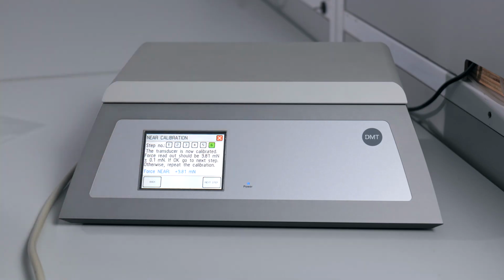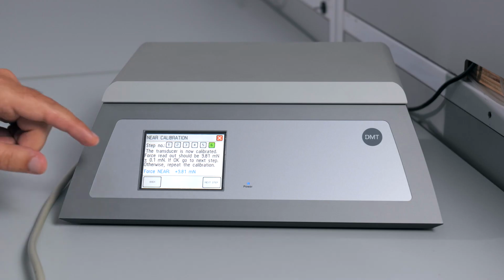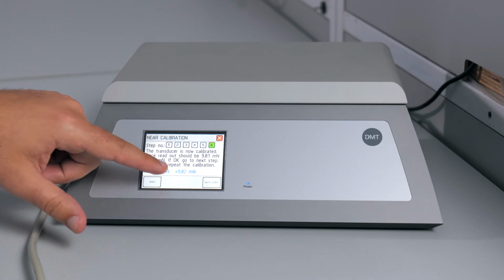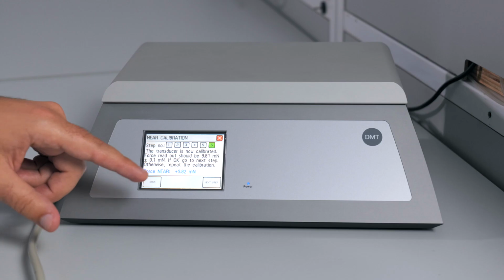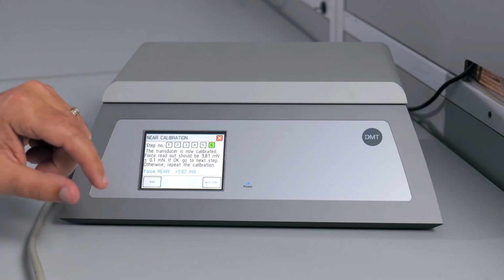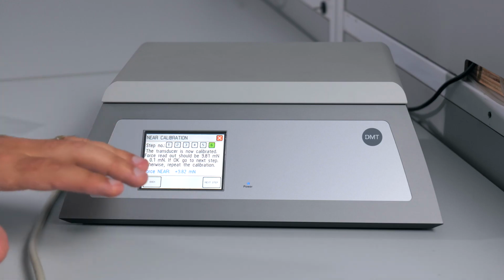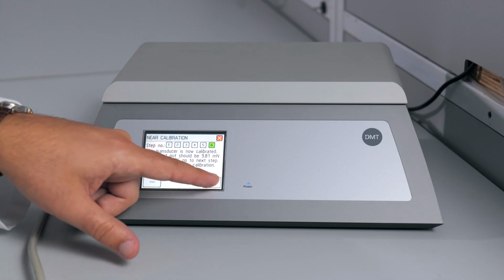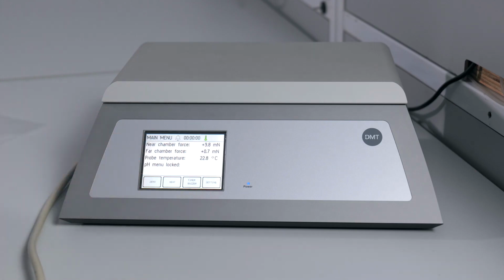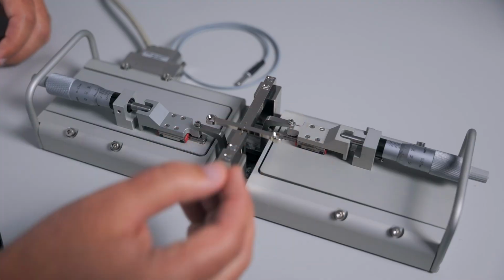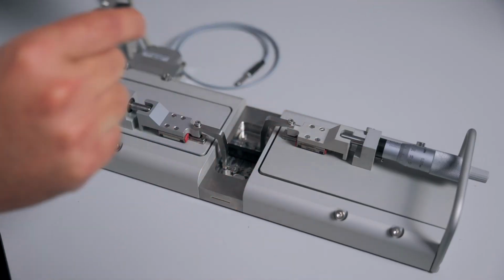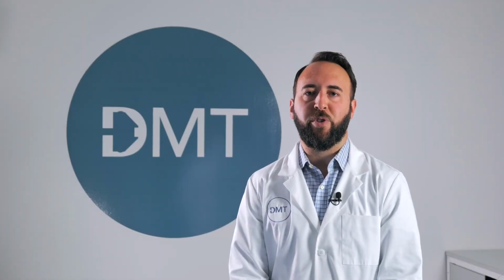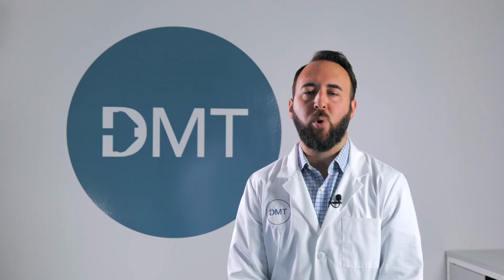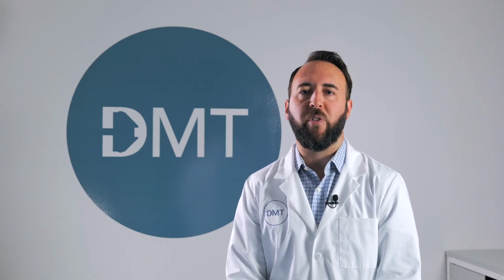The reading should be right around 9.81 plus or minus 0.1 millinewtons. If you're in that range, which we are today, you can go to next step to lock in the calibration before you remove the weight or the calibration bridge. That concludes the force calibration procedure. You can then remove the weight and the calibration bridge. For more information, please refer to the 420A user manual or additional resource videos found on the DMT website.